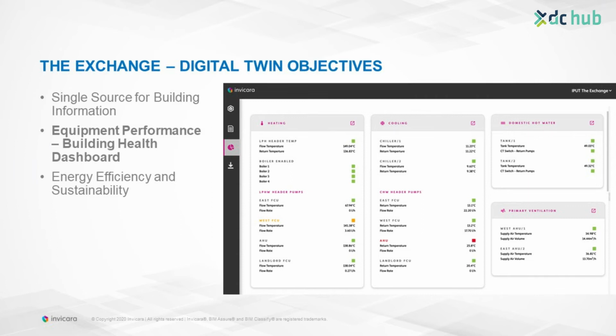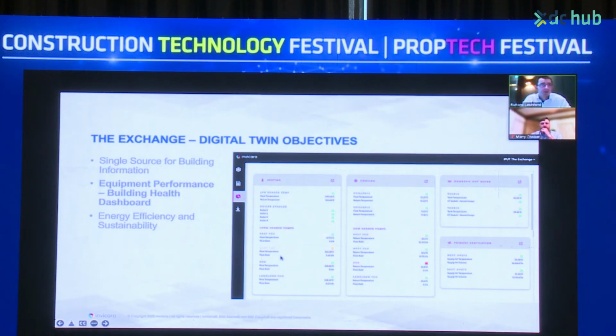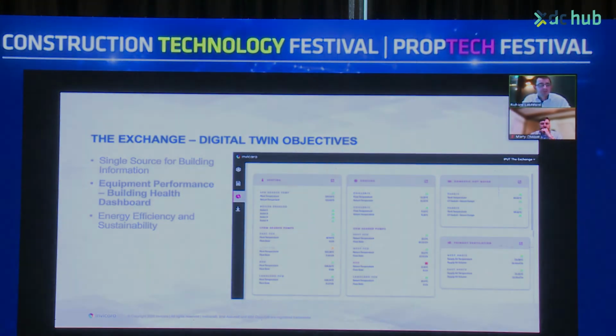We've applied the set of rules Marty referred to earlier. The rule in the case of a boiler may identify that when a boiler is enabled, it should reach a particular temperature within a particular period of time. If it falls outside those parameters, it raises an orange flag, and it may go on to identify a red flag and send out an external alert. So we're in full control of the rules and parameters based on our expectations.